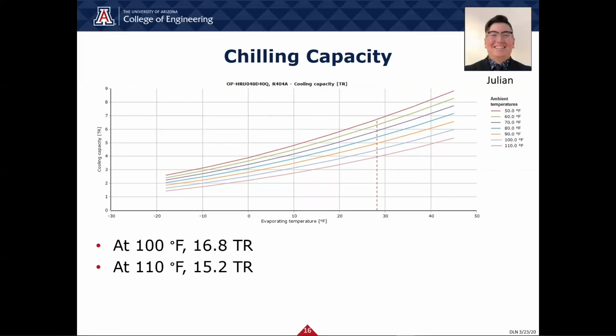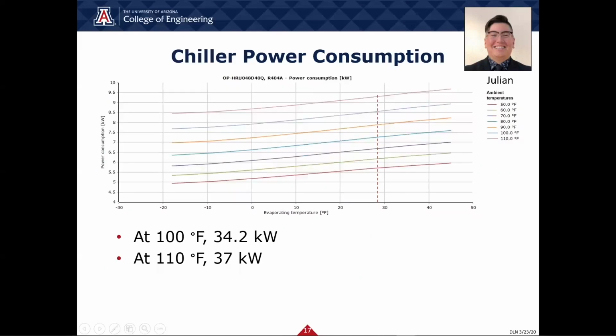From these plots, we gather that the chilling capacity at 100 degrees Fahrenheit was 16.8 tons of refrigeration, and at 110 degrees, it was 15.2 tons. Again, at these same temperatures, the power consumption was 34.2 kilowatts and 37 kilowatts.